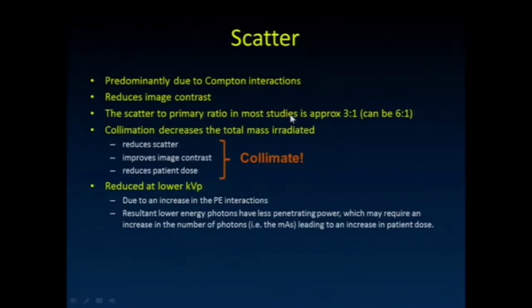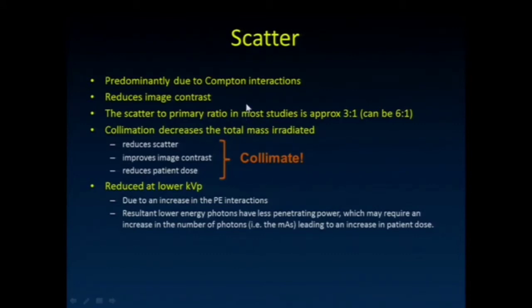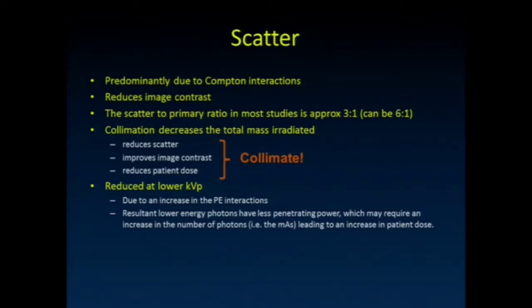I next want to talk a little bit about scatter. We've talked about this really being due predominantly to those Compton interactions. There's a little bit of classic or Rayleigh or coherent scatter as well. This reduces our image contrast. And in a lot of imaging that we do — chest radiograph, pelvic radiograph — the scatter to primary ratio, the number of detected X-rays that were scattered versus ones that were unscattered, can be three to one. Three times as many scattered as opposed to unscattered, or even six to one in lateral abdominal or lateral lumbar spine imaging.